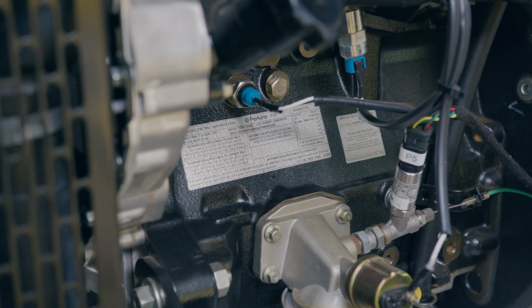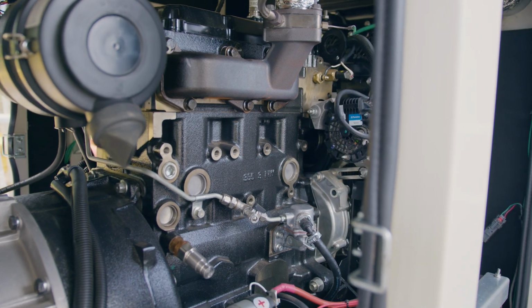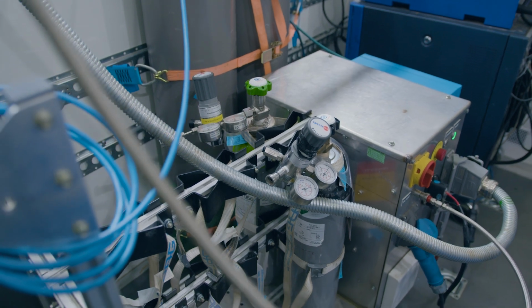Across Perkins' range of engines, from the 400 series all the way through to the 5000 series, all of our engines can run up to 100% HVO. We do look that the fuel is to the EN 15940 standard, an international standard for the quality of the fuel and the level of different chemicals within it. This is only the same as regular diesel, which should be to EN 590, a globally recognised standard, and most fuel suppliers should be able to make fuel to that standard.